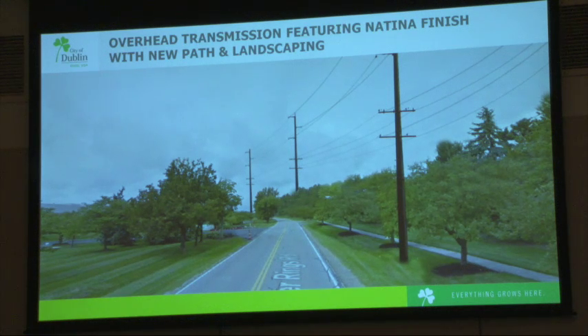When you say overlap, clearance can overlap? So when we talk about this 80-foot corridor being centered on our poles, it means that we are taking easements wherever there are private easements. So if we are 5 foot inside of the private easement, then we will acquire easement rights for up to the road right-of-way and then the existing 40-foot into that. So it could be 45 if we're 5 feet off road right-of-way, 5 feet plus that 40-foot.